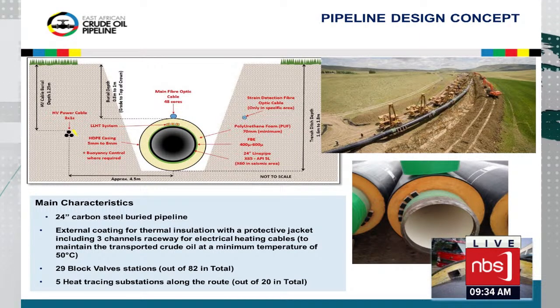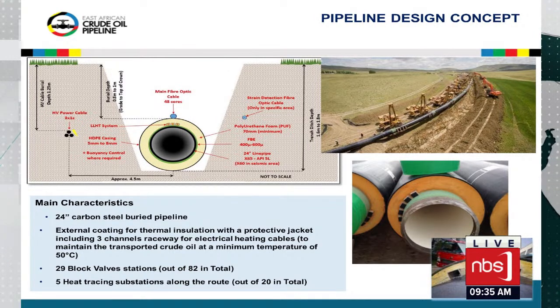A few more technical details about the pipeline design. Something important to mention is that the crude, due to its characteristics, needs to remain always above 50 degrees C to flow. To achieve this, we apply a thermal insulation coating, roughly 70 millimeters of polyurethane foam, on the entire pipeline length. On the picture you see an example of this thermal insulation coating. This activity will be done in Tanzania.